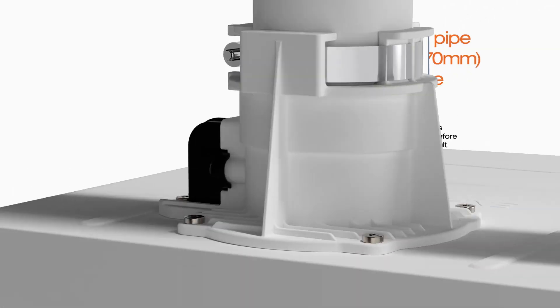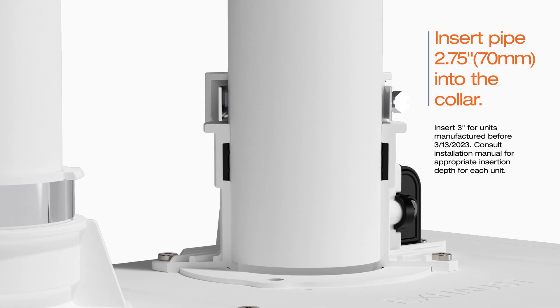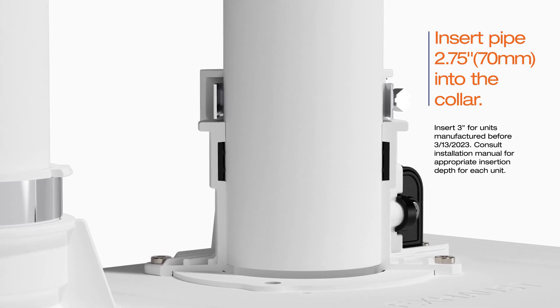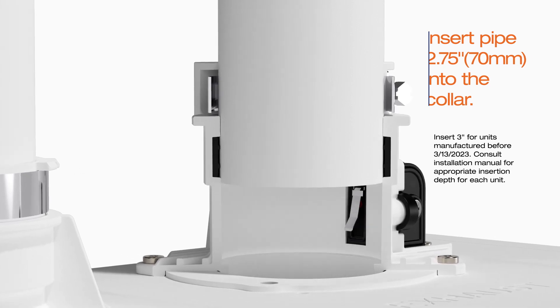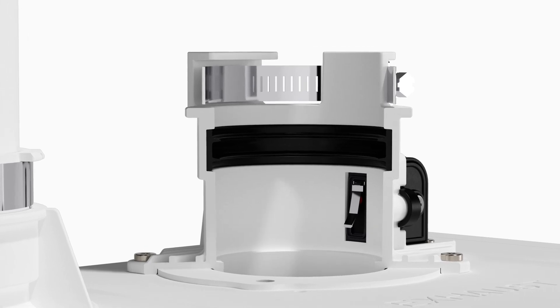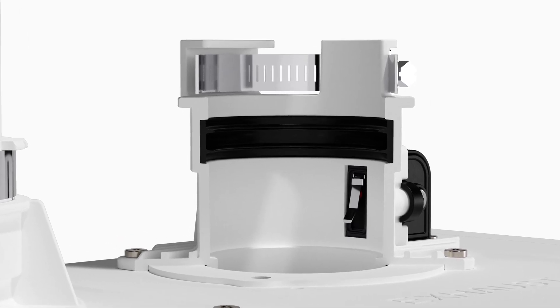Fully insert the exhaust pipe into the collar past the seal to engage the VID. Refer to the installation manual for the required insertion depth. The detector is located inside the vent collar to check for proper pipe insertion.